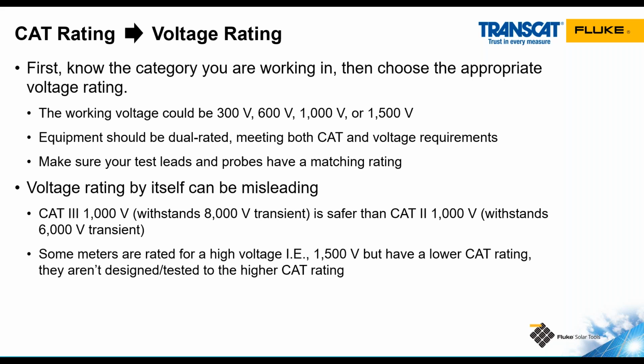When we're looking at voltage ratings, we may have the same voltage of a tool, but if the category rating is different, the safety rating will be different. So in this example, a category 3 1000 volt test tool is designed to withstand 8000 volt transients, where a category 2 1000 volt test tool can only withstand 6000 volt transients. So even though they're both 1000 volt rated, because the category rating is different, the ability to withstand transient voltage spikes is also going to be different.